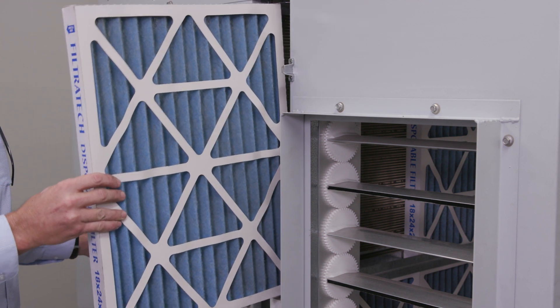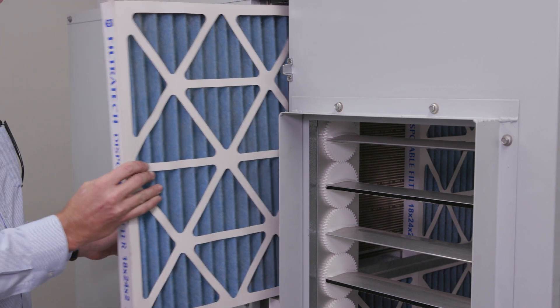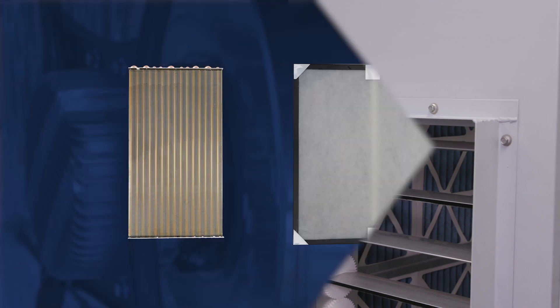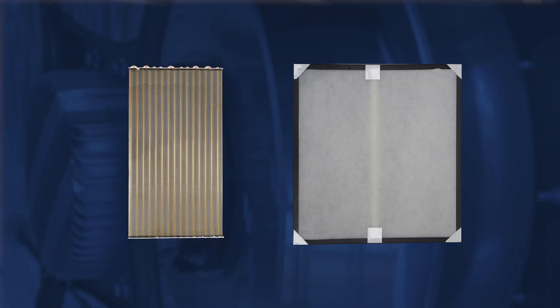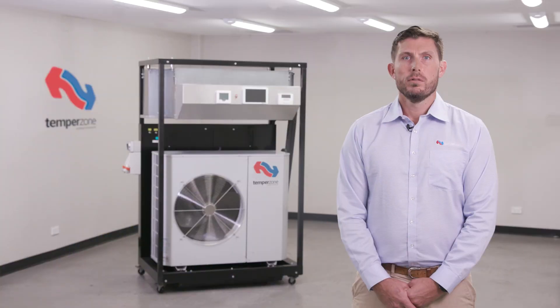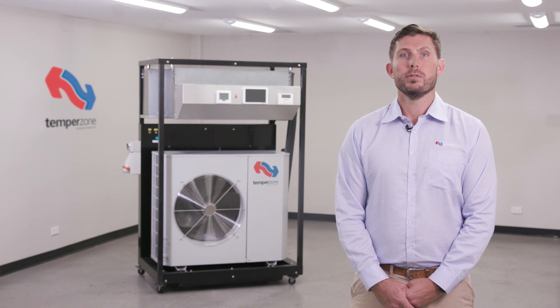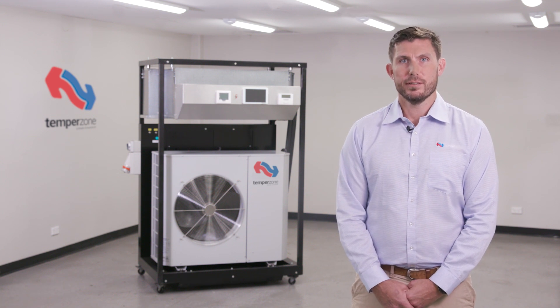The return air filter must equal the same surface area of the indoor coil face as a minimum. It is recommended to select return air filters that have a surface area larger than that of the return air coil. This can be achieved with corrugated filters or multiple grill filters.